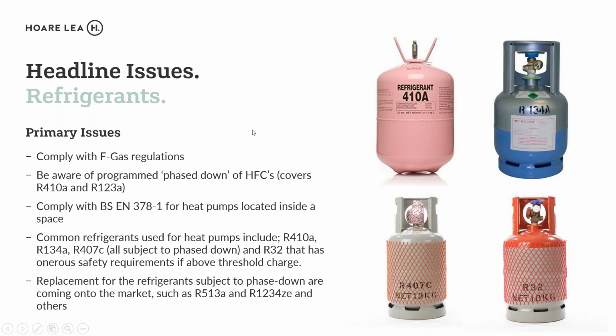Louise has mentioned GWP on the gases, but they are changing with regard to heat pumps. There's a lot going on with regard to R32 at the moment, and also some types of heat pumps that will generate hot water only, heating and storing hot water, rather than just lower temperature heating. That may well be applicable for spaces where you have a high hot water demand. And we are still doing the phase down of the current refrigerants. We've got R513A and 1234ZE coming in, but they're not particularly widespread at the moment, but I can see those coming along to lower the GWP.